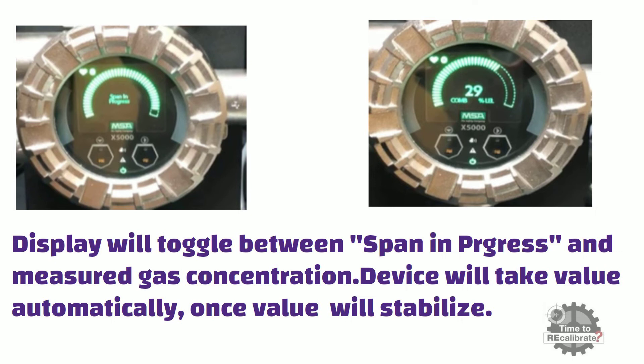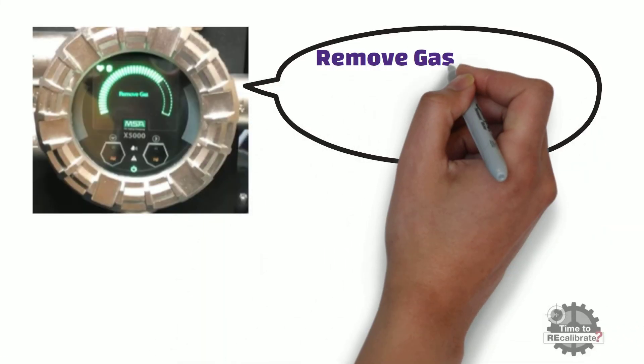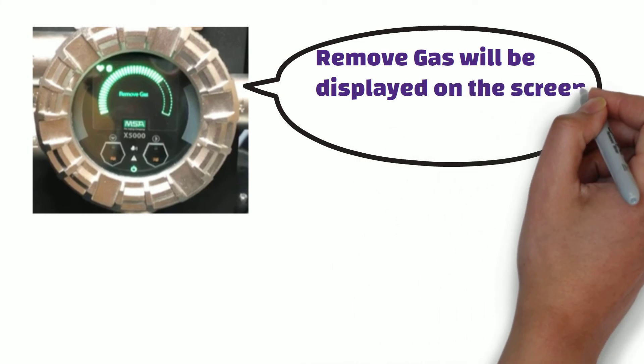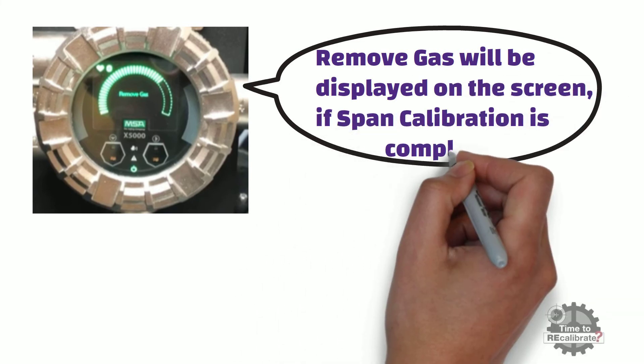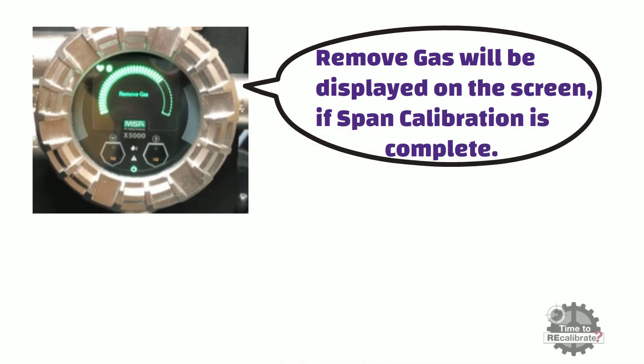At this point, be patient and wait till the value stabilizes. As you can see from the picture, remove gas will be displayed on the screen if span calibration is complete. So, turn off the gas flow and remove the Tygon tube from the sensor at this time.